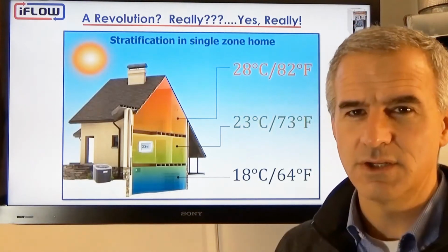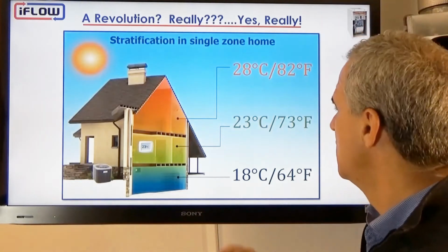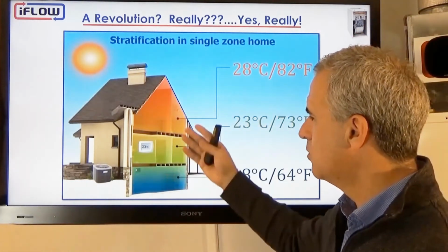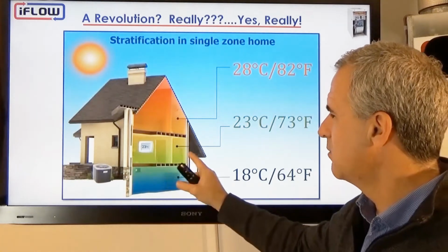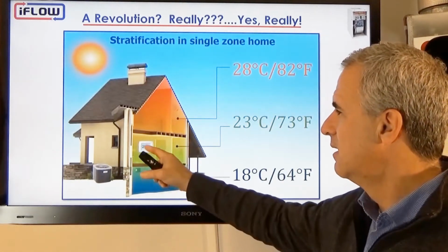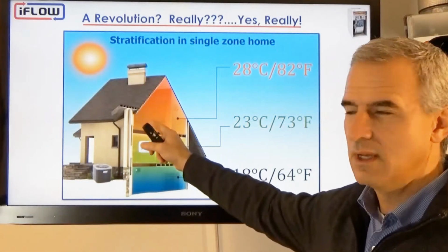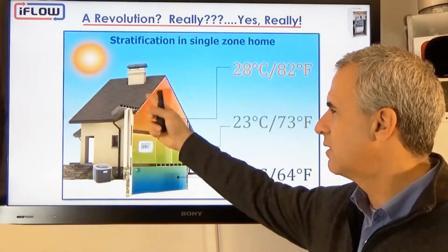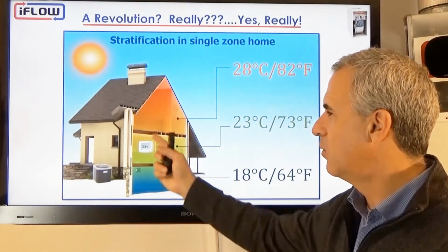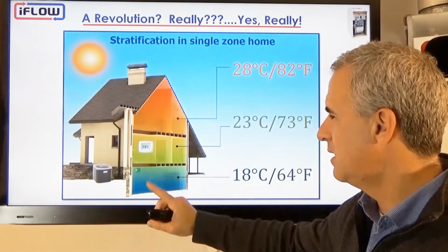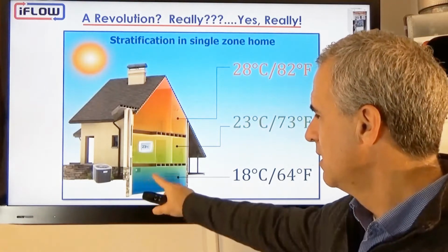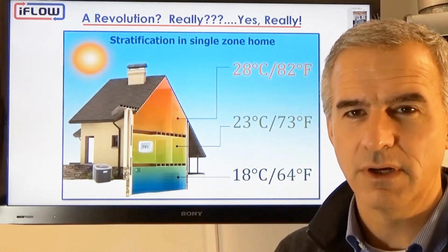Stratification. This is an issue that I'm sure many of you see. You have single zone homes for the most part with the thermostat on the main floor, which may be comfortable, but then the hot air pools in the upper floor. So in the summer your top floor can be very, very warm, when your main floor may be at temperature, and then your basement will be very, very cold.